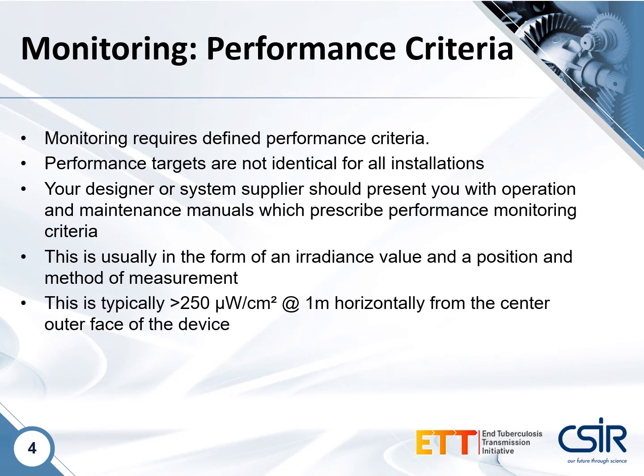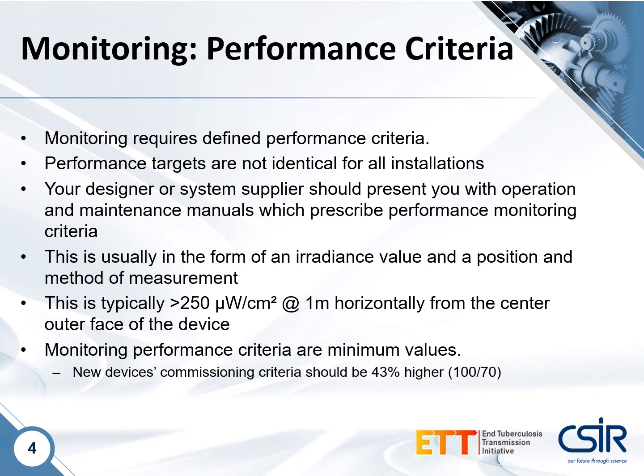In the absence of designer's prescribed monitoring criteria, this value is typically about 250 microwatts per centimeter squared, which should be measured normally at 1 meter horizontally from the center outside face of the device. Note that monitoring performance criteria are minimum values, which means that new device commissioning criteria should be about 43% higher, which is a function of the 70% lifetime depreciation of those lamps.